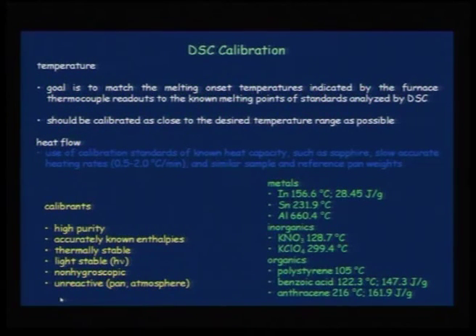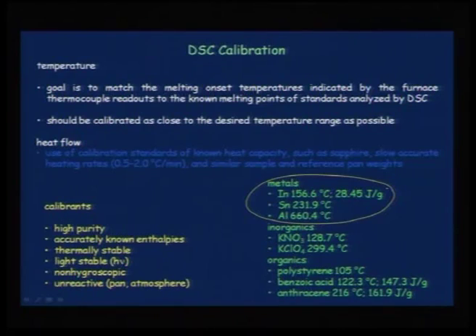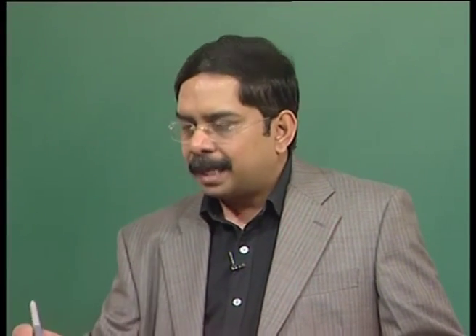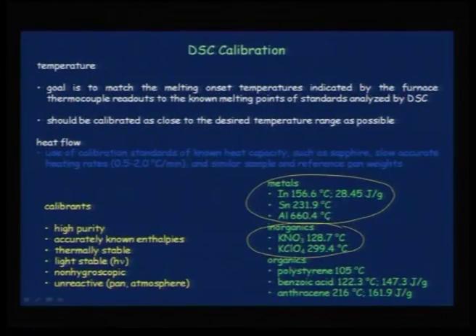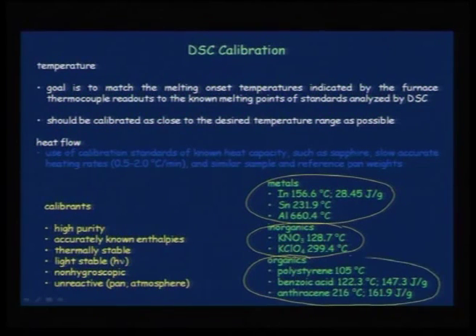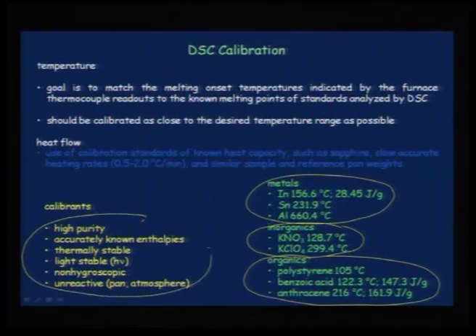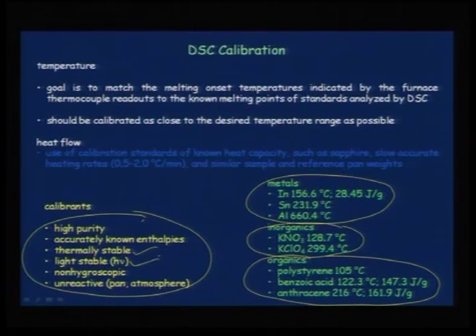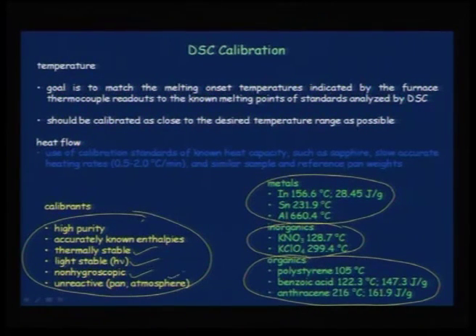DSC calibration can be done with a variety of calibrants: metals for high-temperature samples, inorganics like KNO₃ or potassium perchlorate, or organics like polystyrene, benzoic acid, or anthracene. Important requirements for calibrants: high purity, thermally stable, should not undergo changes with light, should be non-hygroscopic, and should not react with the pan or with the purging atmosphere.